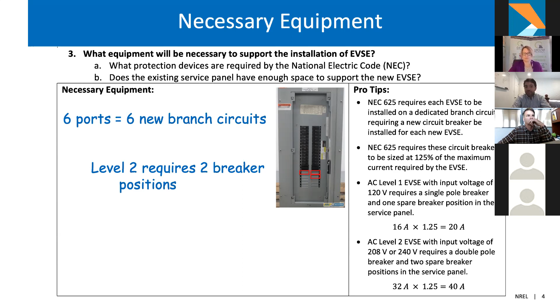As we discussed earlier, level 2 stations require 2 breaker positions, so you'd want to plan to make sure there are 12 breaker positions available in each service panel you're looking at.